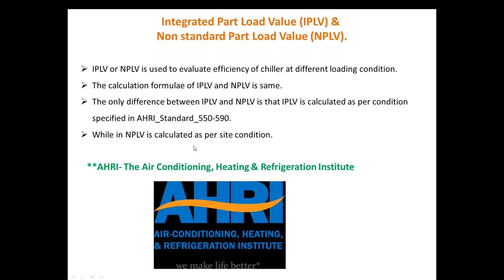If you are not following standard 550/590 and you are evaluating the part load value or performance of your chiller based on site conditions or local conditions, then it is called as Non-Standard Part Load Value. So IPLV and NPLV use the same formula — the only difference is the condition under which you are testing or trialing your device.